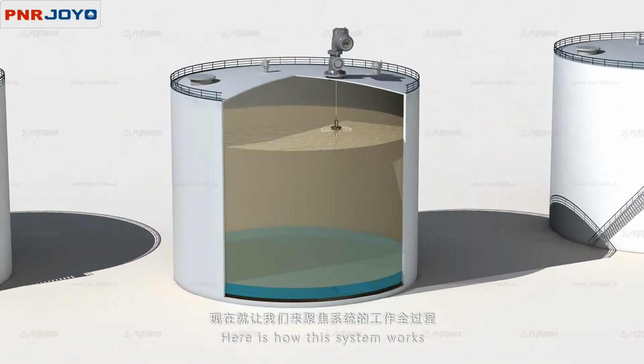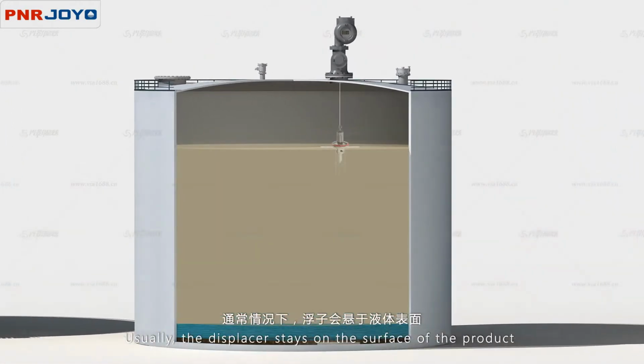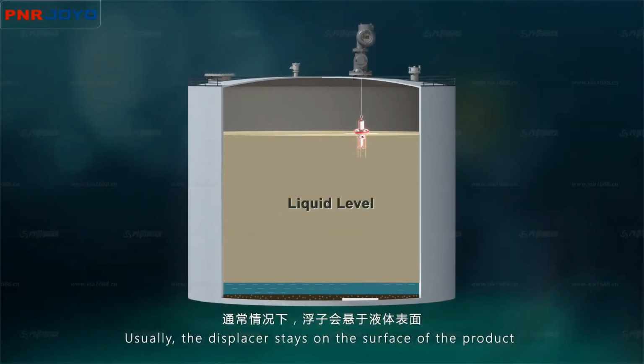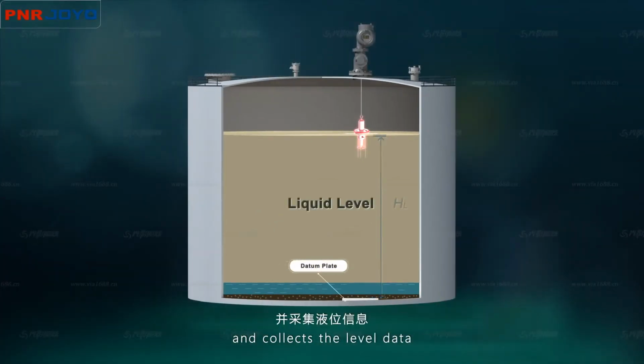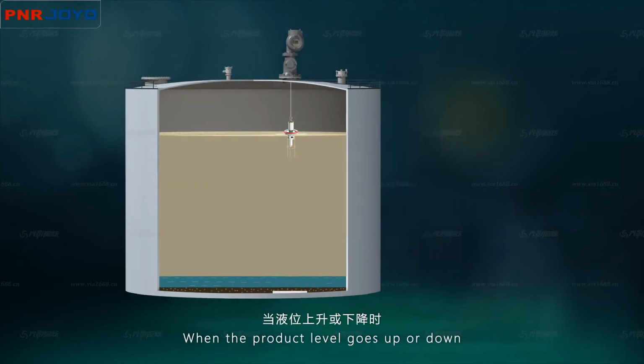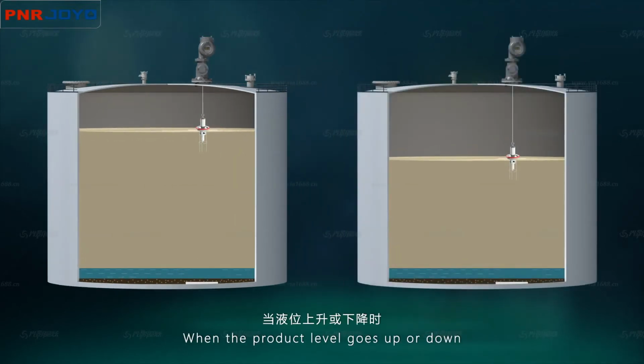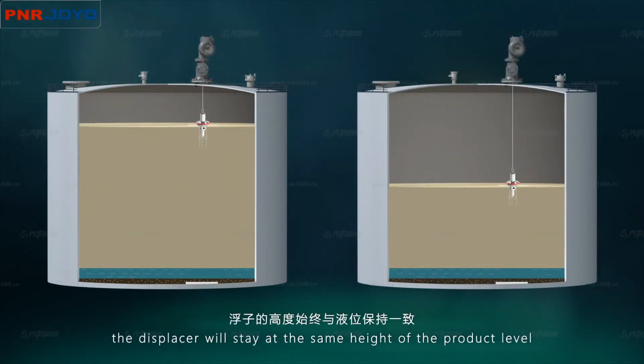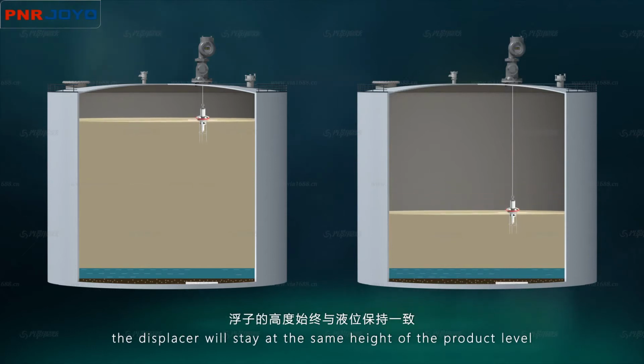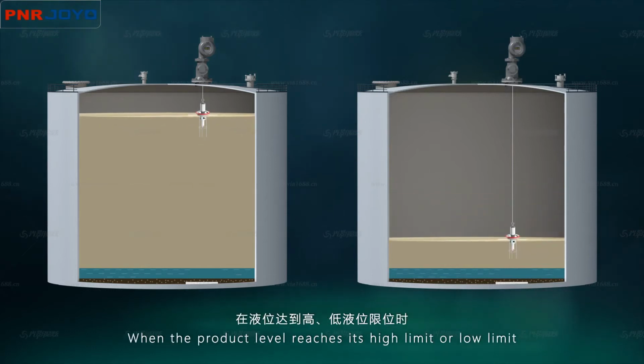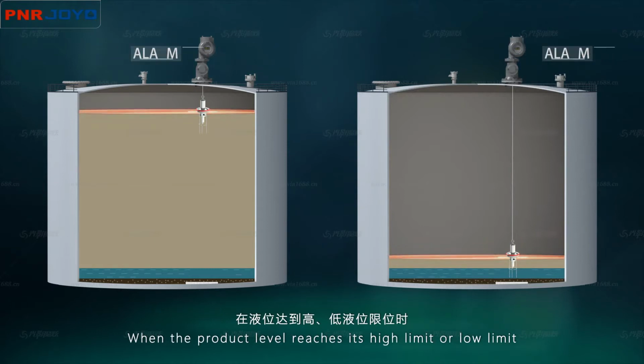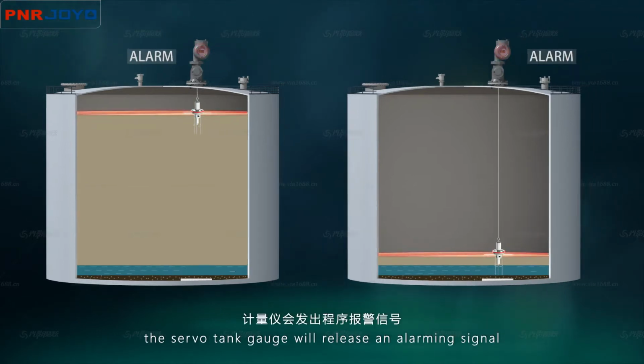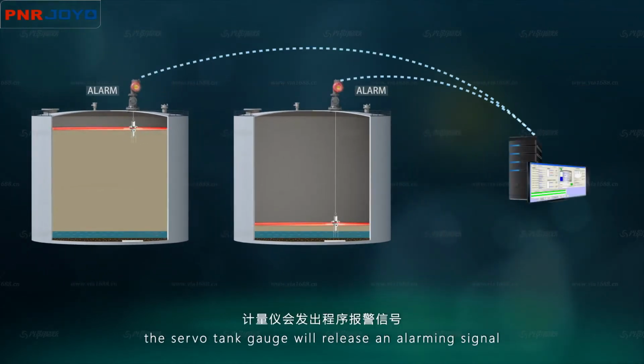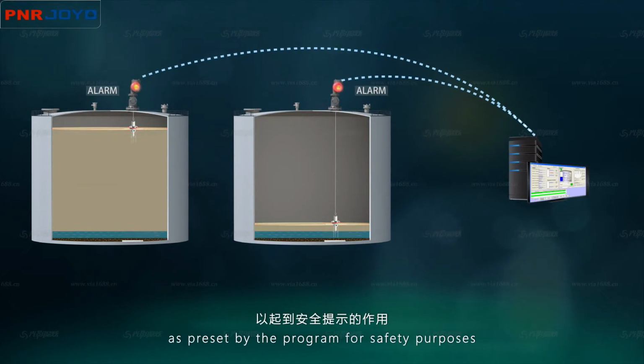Here is how the system works. Usually, the displacer stays on the surface of the product and collects the level data. When the product level goes up or down, the displacer will stay at the same height as the product level. When the product level reaches its high limit or low limit, the servo tank gauge will release an alarming signal, as preset by the program for safety purposes.